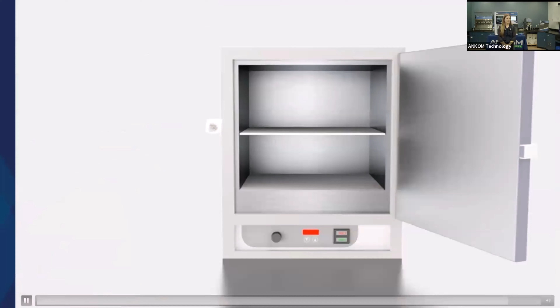So that video gives you a great overview of what is happening inside this piece of equipment. Once you put your filter bags inside this equipment, you press start and the user can walk away. As I mentioned, the automation is enabled through our filter bag technology. Filter bag technology will replace your glassware because each filter bag, you would weigh your sample in, seal it, and then place it in that bag suspender that you saw in the video.